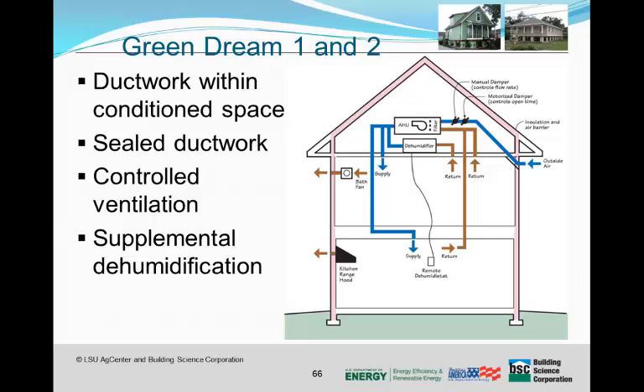When a home is very energy efficient, it can get to a point where you don't need much heating and cooling. That's the whole idea, to make it real energy efficient, reduce your bills, reduce your heating and cooling loads. But that doesn't reduce the dehumidification load that we have in our warm, humid climate, so supplemental dehumidification was provided so you can have good indoor air quality and good comfort, whether or not you need any real heating or cooling of the temperature.